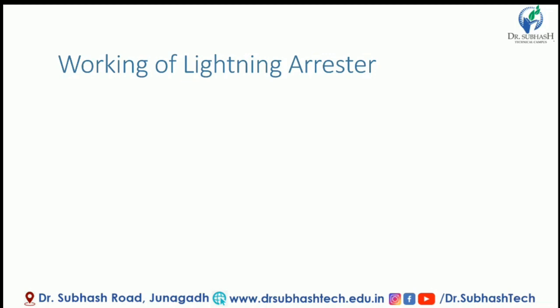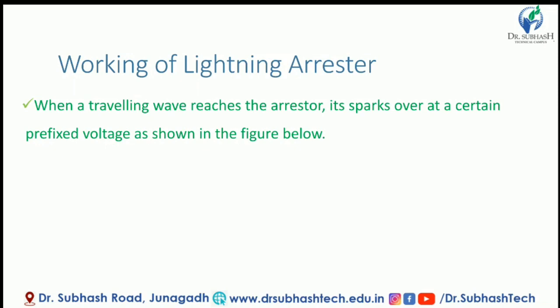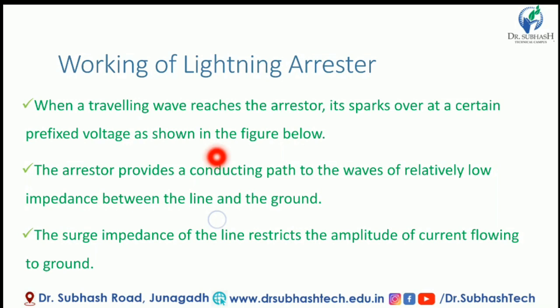When a travelling wave reaches the Arrestor location, the Lightning Arrestor sparks over at a certain prefixed voltage. The Arrestor provides a continuing conducting path to the waves, with a relatively low impedance path between line and ground. The Arrestor provides a direct path to the waves, and the surge impedance of the line restricts the amplitude of current flowing to the ground.